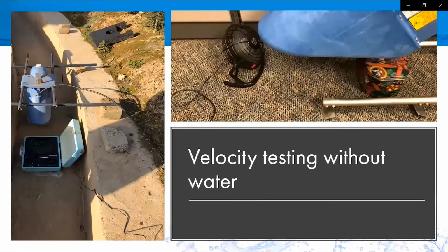Other things you can do to test a LaserFlow system if you don't have water running: here they put a record player down there. The laser can read the speed of the record spinning, and the velocity changes, getting faster as you get to the outside and slower closer to the center. Or what I like to carry with me is just a little USB fan. It's a quick and easy way to test the mechanics of your system to verify that it is actually reading the level and velocity.